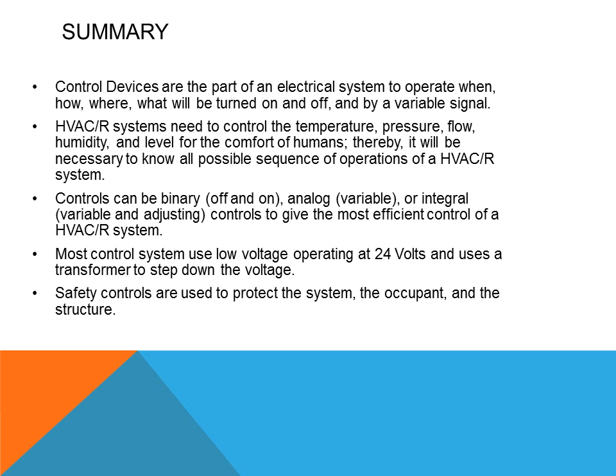Controls can be binary, which is on and off; analog, which is variable; or integral, which is variable and self-adjusting, to give the most efficient control of HVAC systems. Most control systems use low voltage operating at 24 volts, even though commercial systems can have higher control voltage, but will still use transformers to step down the voltage. Safety controls are used to protect the system, the occupants, and the structure.